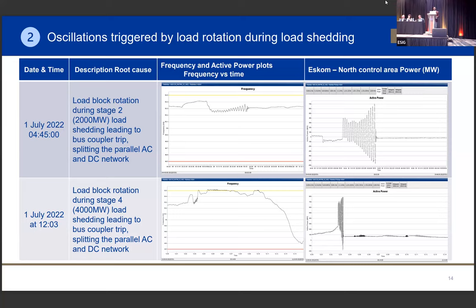So here, while we were rotating load, the frequency climbed up to about 50.4. Then that triggered the bus coupler at Songo from the GMPSC. Then we started having oscillations. On the graph, in the middle is a frequency plot, and on the right is a power plot. We measured from our side, but we saw the oscillation from our neighboring countries.